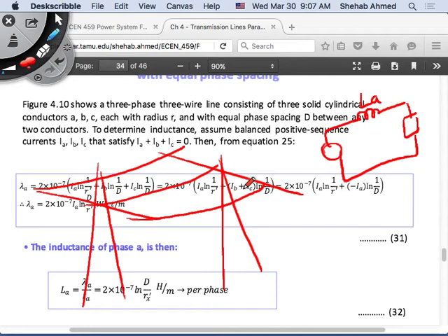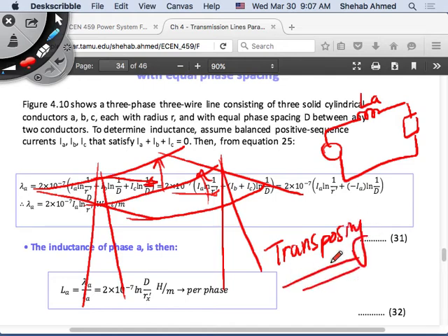No, you never pay attention. If you drive by a transmission line for several kilometers, for example, you will see that they will swap places. They will switch places, and it's called transposing. It's called line transposition. This line transposition is to deal with this.